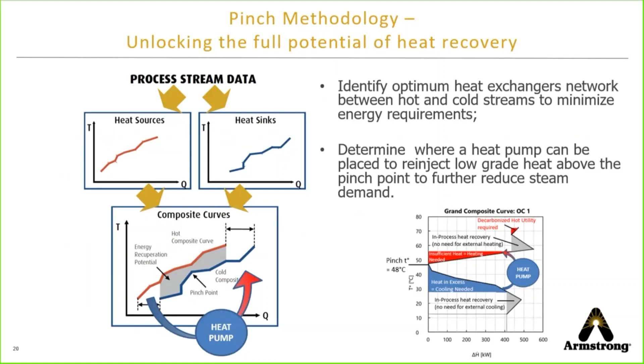So we'll get a heat source curve, we'll get a heat sink curve, we'll combine those together to determine where we can, again, use direct heat recovery, and then where those points are above or below where we're going to need cooling, we're going to need heating, where potentially a heat pump could come into play. So we'll go through and do all these studies. We'll deliver this data to you. There'll be a lot of back and forth.